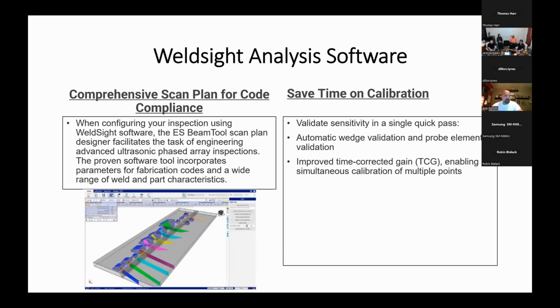So with WeldSight, essentially what you can do on here is you can set up and build your entire scan plan prior to going out and inspecting your part. So it's used with ES BeamTool. So you have access to a full library, catalog, probes, and wedges. You can build your scan plan through ES BeamTool and then import that into the X3, which also gives you an overlay of the part as you're scanning as well.